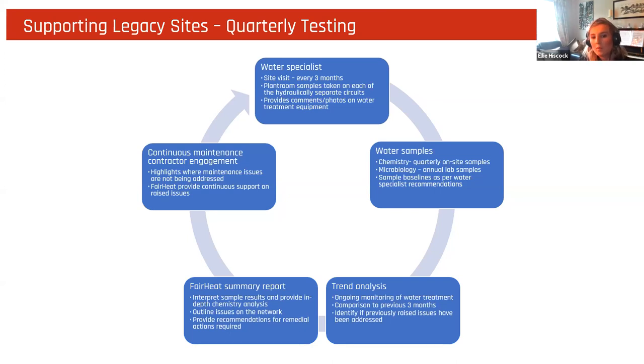So we typically carry out quarterly visits, which include on-site chemical analysis, which will monitor things like pH, alkalinity, inhibitor levels, as well as recording the status of water treatment equipment, such as whether it's online or offline. But these visits will also include an annual microbiology sample, which is sent off to the lab. And these are only really required annually, provided that there is no previous bacterial growth detected. Then due to the fact that it's a closed system, it's relatively minimal risk that it will suddenly appear. But from results obtained at the site, we then carry out trend analysis to see how the system may have changed from previous visits, and then provide a summary report with recommendations.